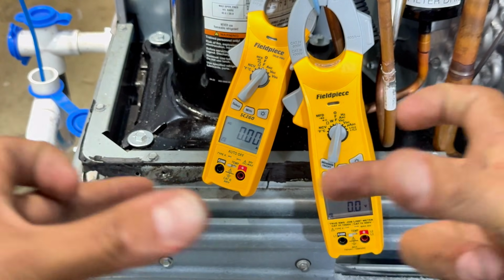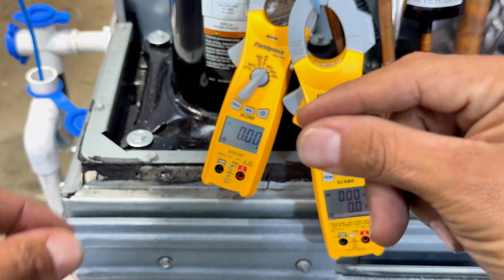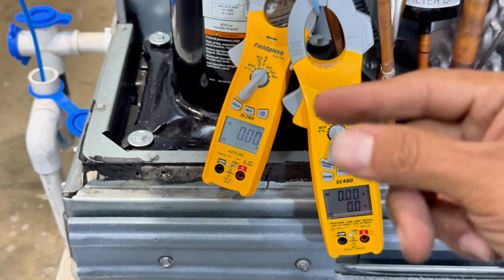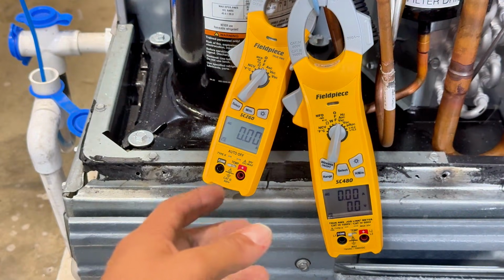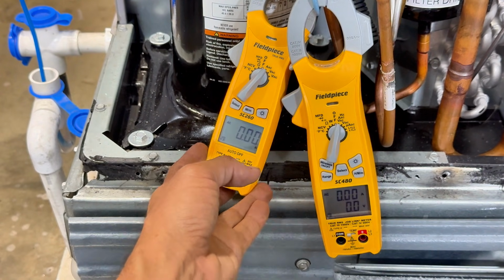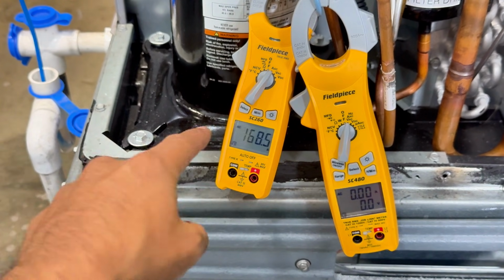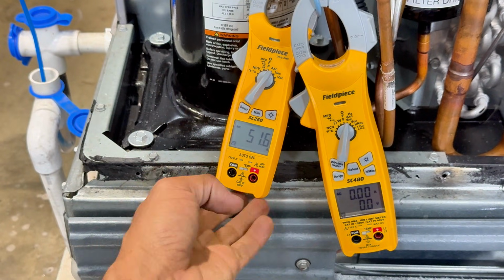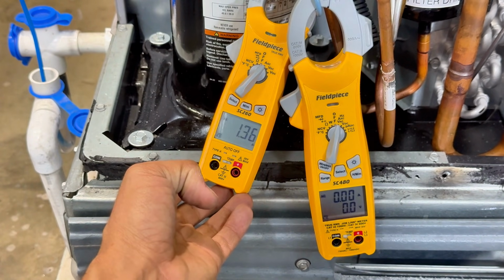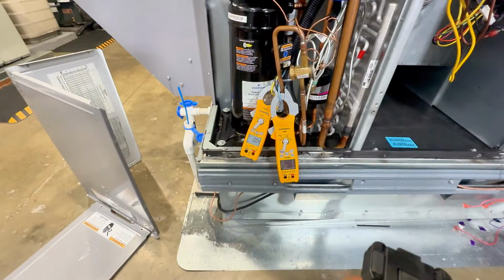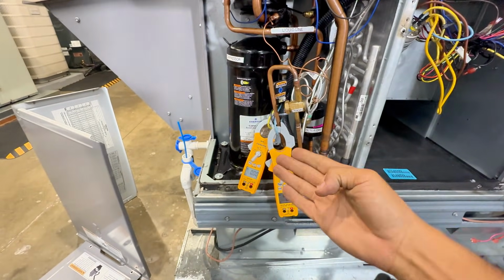So that heat is just being collected and there's a little safety inside the compressor and it opens. So let's see if it does it again. There we go, 52, 51. That's a lot of amps and boom, because it opened. So I just wanted to show you that little trick, right? That's what locked rotor amps is.